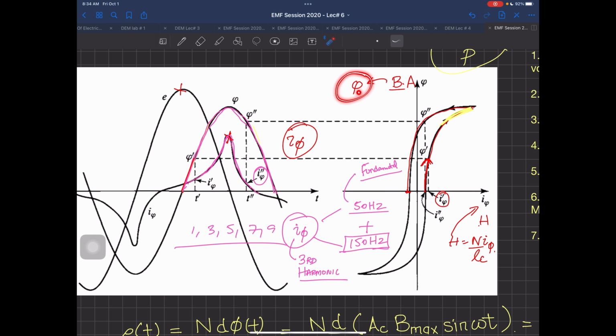So when flux is required, what they do is they make B higher and area smaller. But by increasing B, you get a current waveform with a very sharp rise. When this current is taken up by the supply, this waveform is called the in-rush current of your transformer, because it's a huge spike rushing inside your transformer.